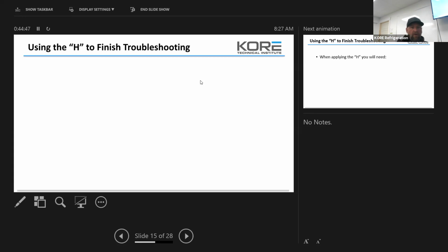Okay. Heat load, using the H to finish the troubleshooting. Up until this point, I have only used a meter and my senses. We have not pulled out gauges until now. This is the point where, if necessary, we pull out some temperature clamps or K thermometers and our gauges. What I will tell you about gauges is that there are specific types of gauges you need to use for specific types of equipment. Do not use 6-foot hose gauges on a fractional charge system. You're going to be there a long time because you just messed with the charge.